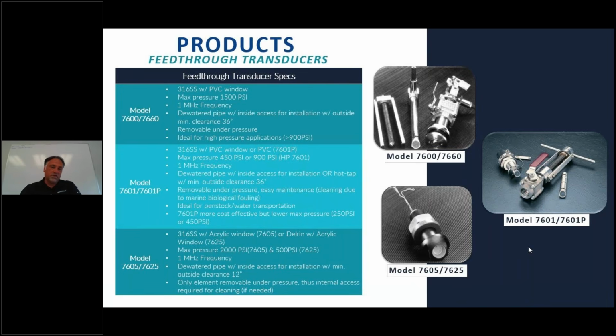And then finally, our third option for the hydroelectric industry would be 7605s and 7625s. The 7605s are constructed of 316 stainless steel and are good to a much higher pressure, 2000 psi, whereas the 7625 is made from a Delrin material, and those are good to 500 psi. The main difference on the 7605 and the 7625 is the transducer element is removable under pressure, but the window is fixed. So the window cannot be cleaned without dewatering the pipe. That's why we typically lean towards the 7600s and the 7601s.